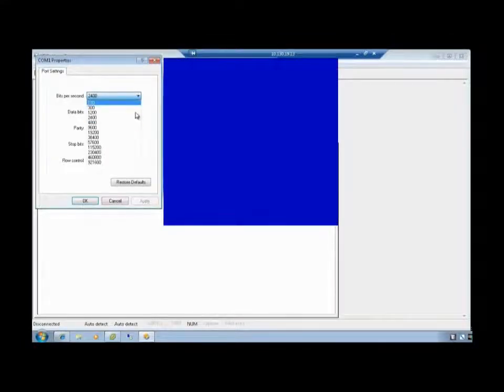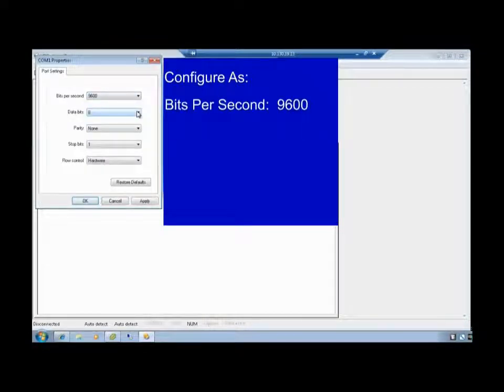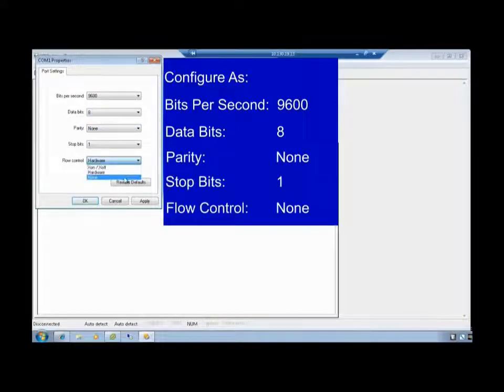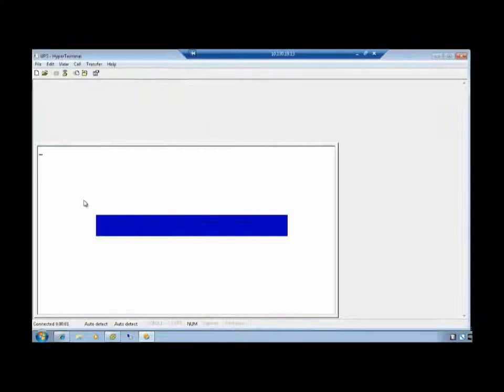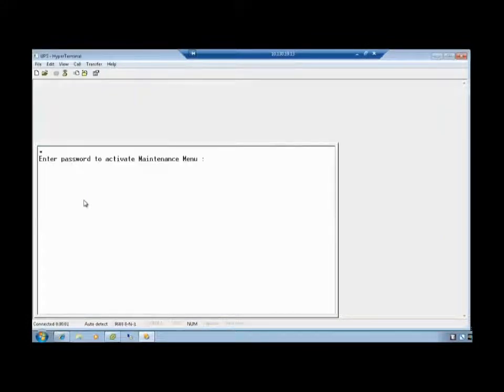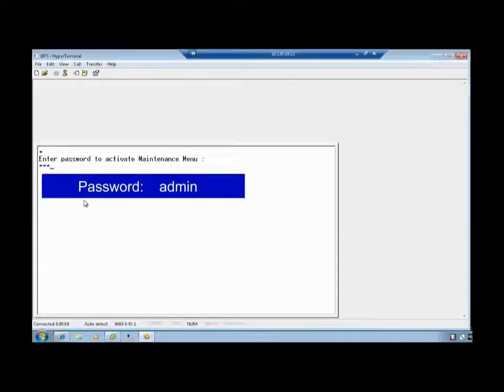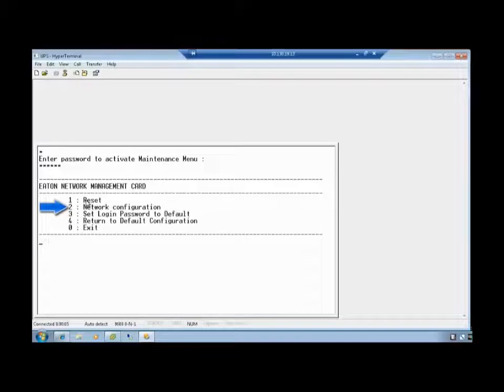Select the COM port properties. Configure as bits per second 9600, data bits 8, parity none, stop bits 1, flow control none. Select OK. Once the screen opens, press Enter to proceed. Activate the maintenance menu by entering the password of admin in all lowercase. Press Enter. Choose option 2 for network configuration by typing the number 2.